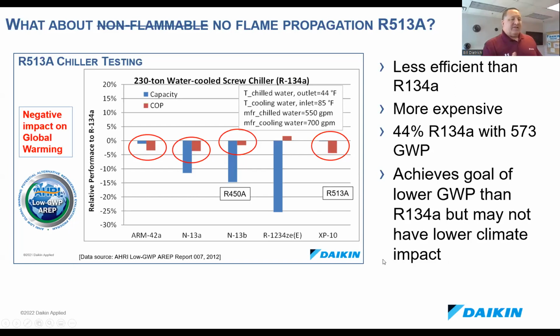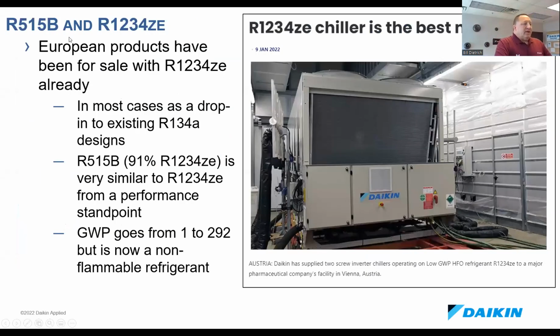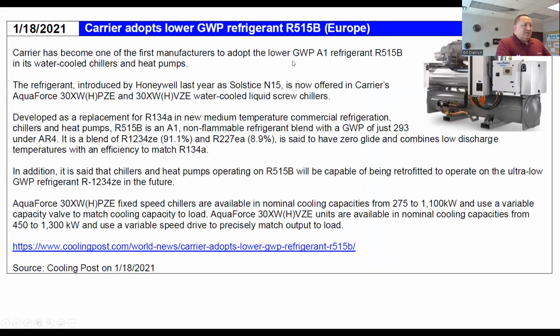I see 513A being like 407C was when R22 started going away. It'll be here maybe for a little while, but I really see the ZE as the long-term product, kind of like 410A displaced R22. We're already seeing it in Europe, because Europe is quicker to embrace slightly flammable refrigerants. Here is a ZE chiller that was sold for a pharmaceutical application. Here, Carrier announced that they're putting R515B in some of their products. So we've seen a lot more of this move a bit quicker in the European market, and we're going to get there. It's just not quite as fast.